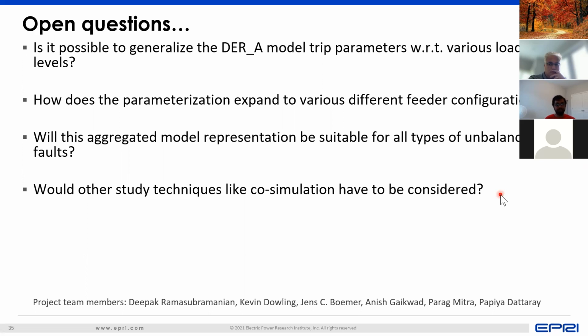I think what else comes about is applying good engineering judgment to carry out a set of sensitivity studies and to define the sensitivity study boundary, to go from a conservative approach to maybe an optimistic approach and find out what lies in between. Then collect data with respect to the various levels of interconnection coming in at the distribution level. One of the main challenges that we saw at the transmission level is this lack of observability into what is happening in the distribution system. So collecting the data in the distribution system environment and coordinating with transmission planners to transfer the data will really help in increasing visibility.